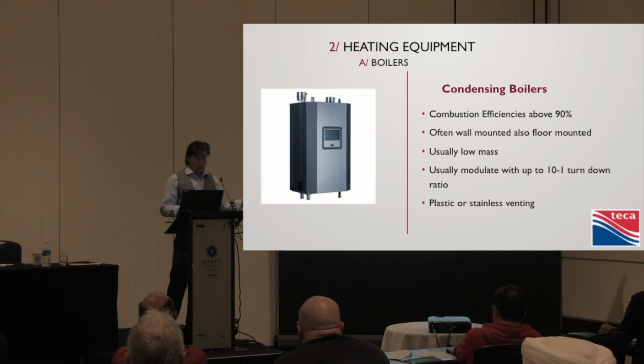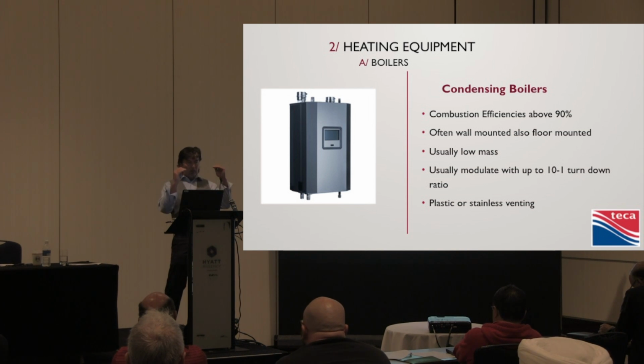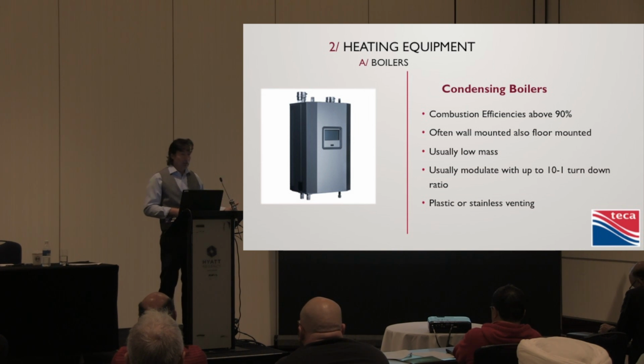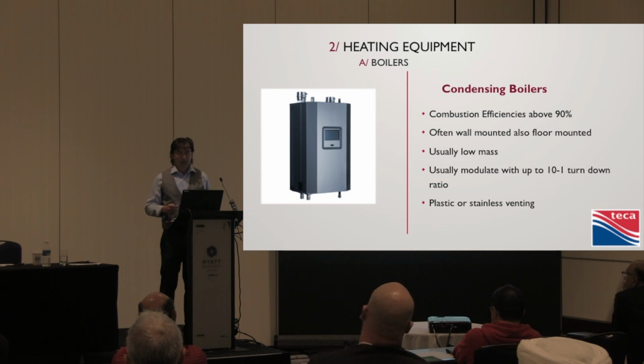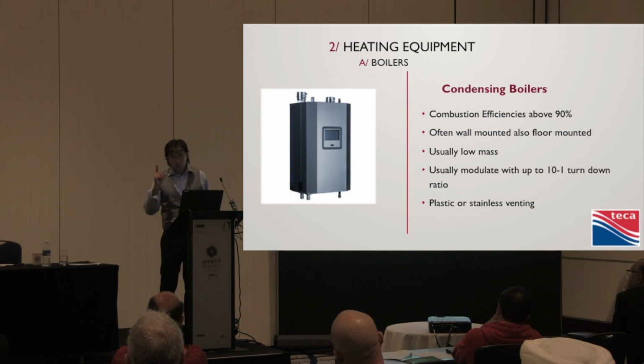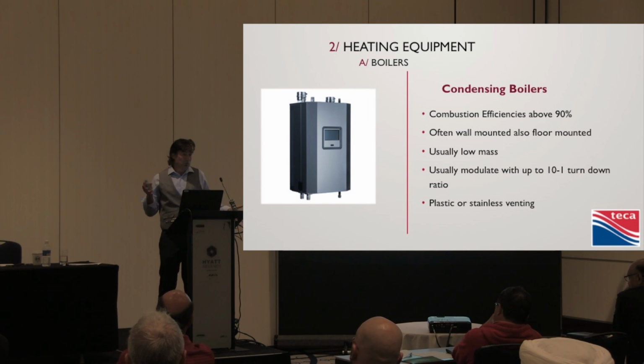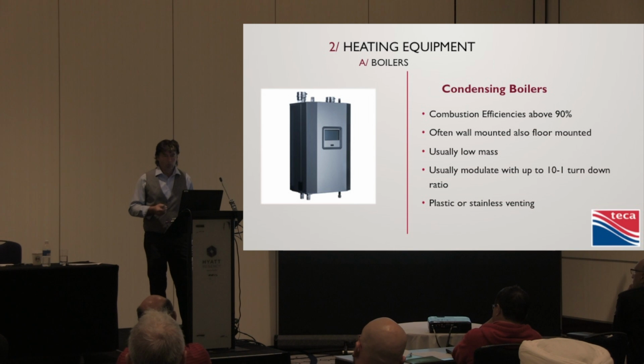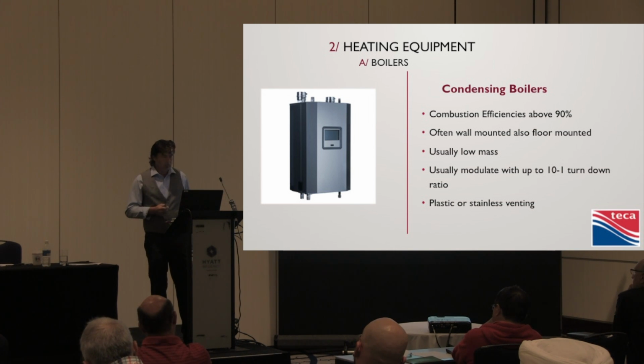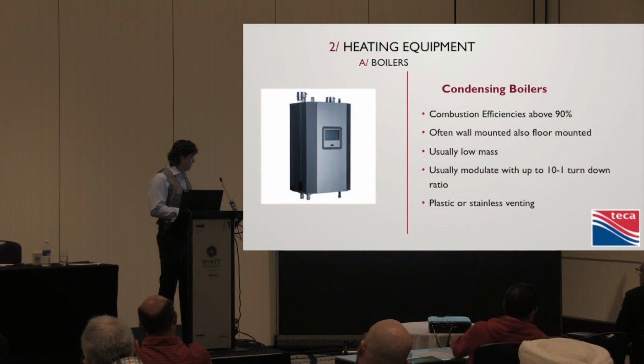Forget about the combustion efficiency. How about we load match? How about we ramp our boiler down? Because in the old days, you'd have your boiler that comes on. It's a 100,000 BTU boiler. It comes on. You might have one radiant zone open. And out of a 5,000 square foot house, you might have one radiant zone that opens, and it actually cools the supply water temperature down. So the boiler aquastat says, click, yeah, I'm below my set point temperature. I'm going to come on. What am I going to come on with? 100,000 BTUs to deal with, say, a 5,000 BTU load. Load matching. Very, very critical. So this is what condensing boilers do for us. This turn-down ratio, very critical.